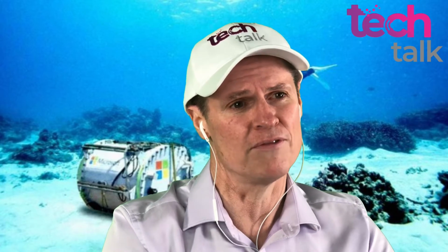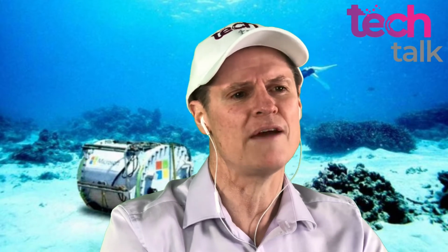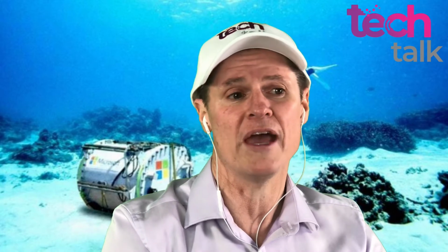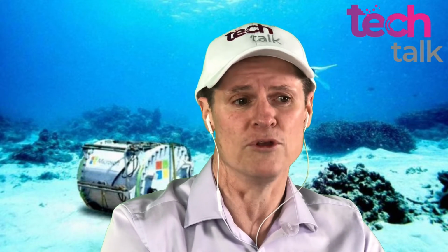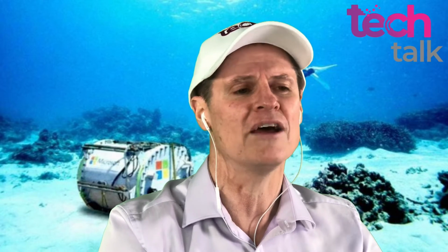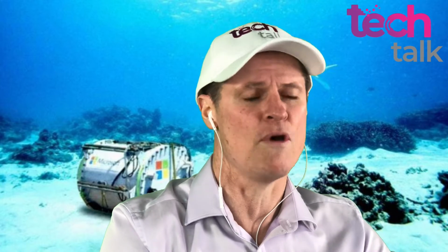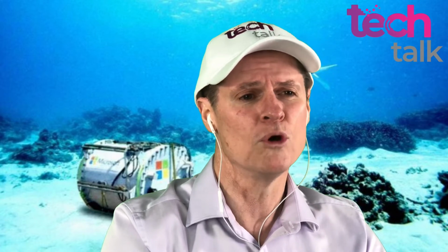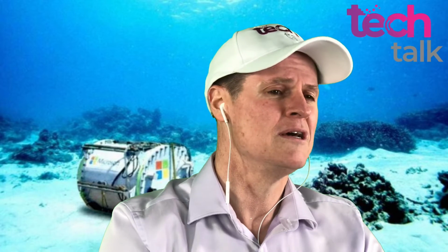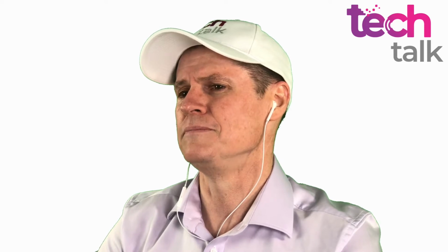So they put it down in an area of the ocean that was quite cool. They used that to see how it went, and they actually filled it with nitrogen rather than having it filled with oxygen to see whether or not that was actually better for the servers. And what they found was when they pulled it out, they had a lower server failure rate than they would in a normal data centre. And they put that down to maybe less corrosion without oxygen in the air. They only had 8 of the 855 servers fail during the experiment. And they also found that the overall costs of running it, so in other words, the cooling costs, were such that effectively it was actually cheaper to run. So will we see lots of our data centres on the bottom of the ocean going forward? Not sure they've got to that point yet where they'll start dropping lots of them down, but it was an interesting experiment. Out of the cloud, eh?